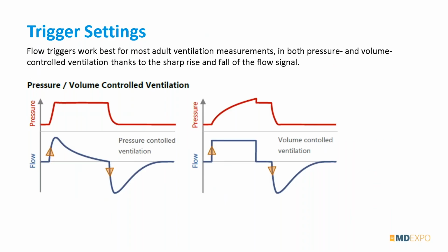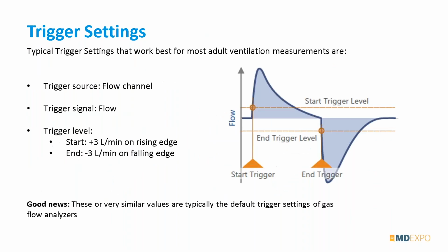analyzer, we have waveforms that look either like this if we are in a pressure controlled ventilation, or like this in a volume controlled ventilation. And as you can see, the flow waveform always has very nice rising and falling edges at the transitions of each breath phase. And additionally, we have a zero baseline that doesn't really change with the settings of the ventilator.